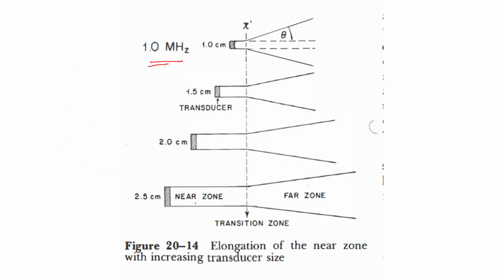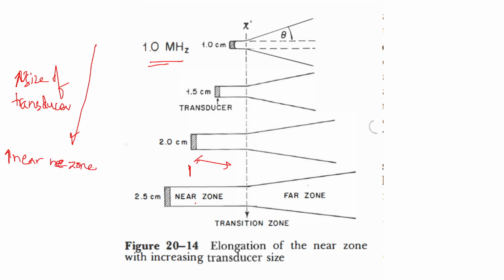Next, here, if you see, the frequency is constant. In the next image, we have made the frequency fixed at 1 megahertz. So here we are increasing the size of the transducer. As you increase the size of the transducer from 1 to 2.5 centimeters, again the near zone increases. So there is an increased near zone seen with increasing the size of the transducer. So whenever the frequency is increased or the size of the transducer is increased, there is an increased near zone or Fresnel zone seen.